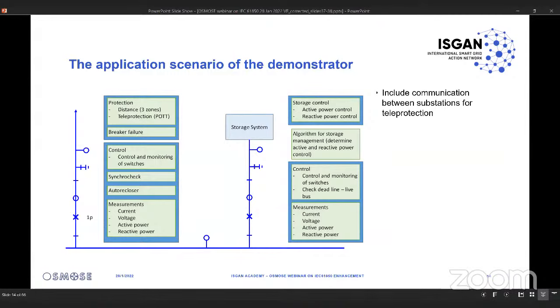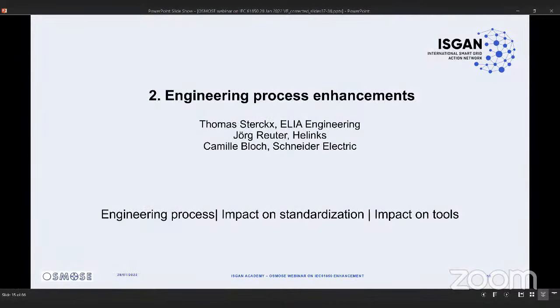We added a storage bay to that substation, which was used to manage overload of the line. The substation was built twice so we also had communication between the two substations, connected through the modeled line. This allowed us to test engineering exchange between the two applications, which is part of the IEC 61850 engineering process. That was our playground for the demonstrator and for our work in the OSMOSE project.